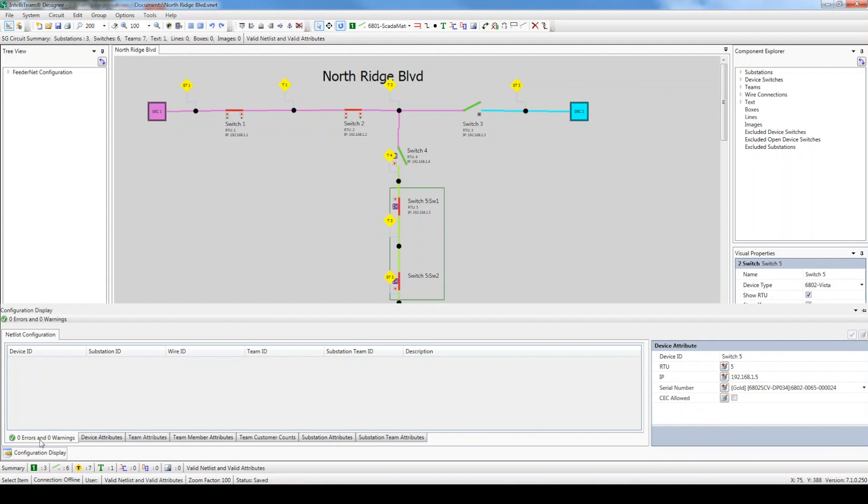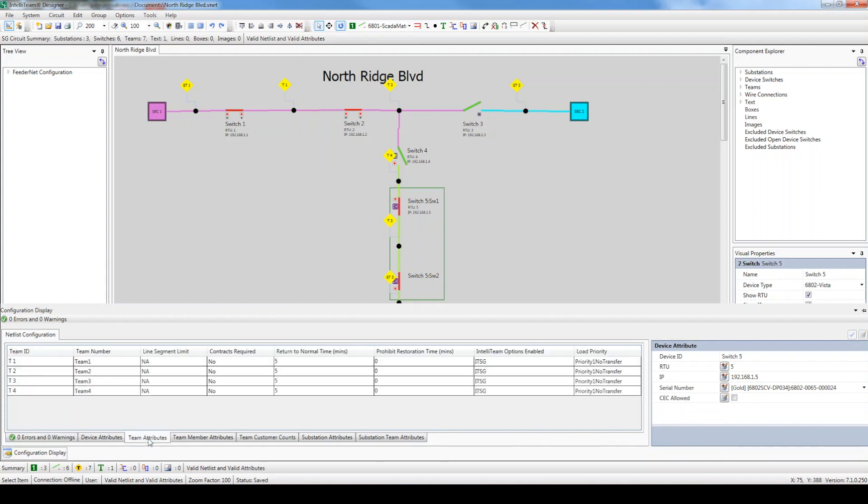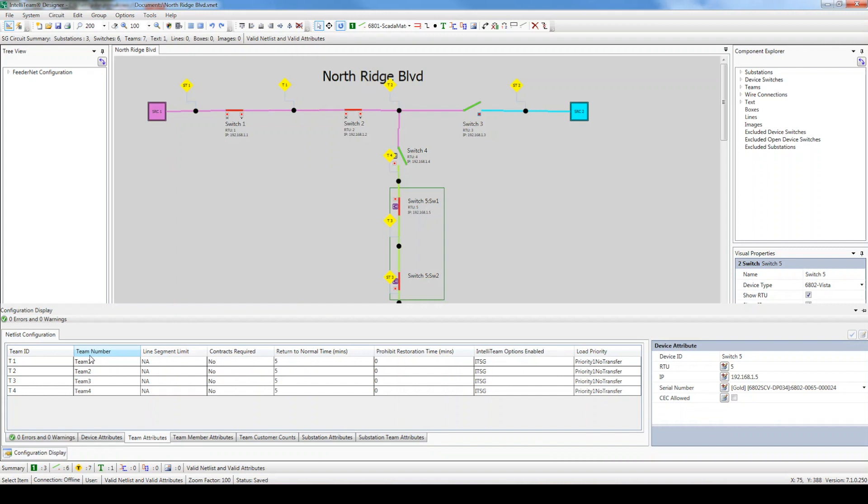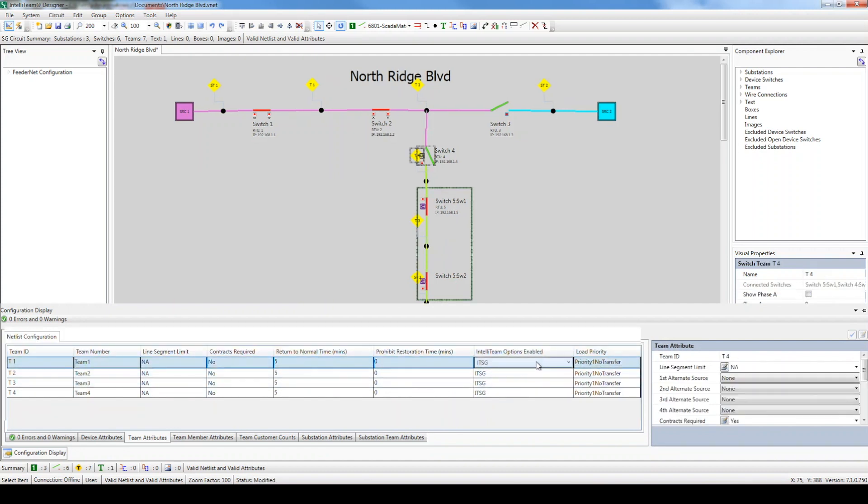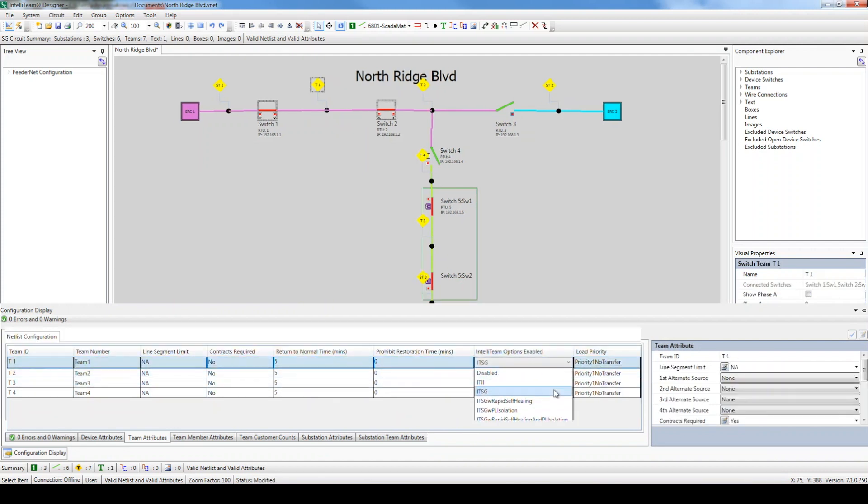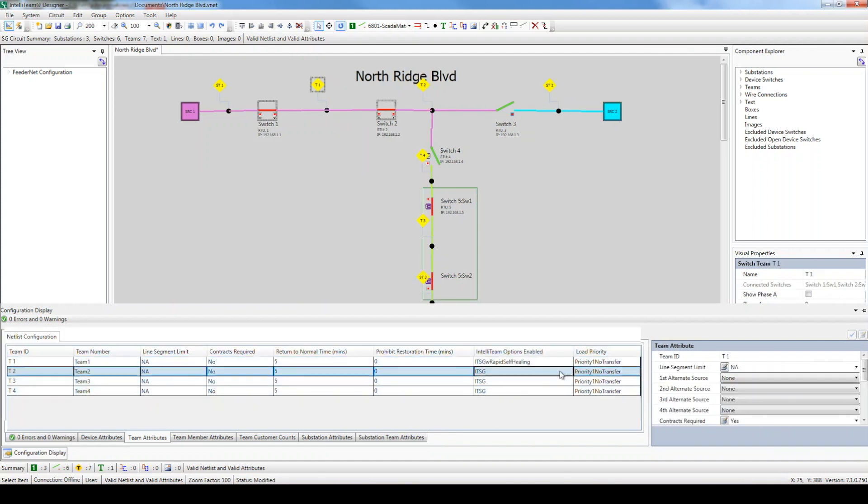Next, click the Team Attributes tab. This is where you configure the settings related to each team of devices. The first two columns display the team identifiers, which are generated during the validation process. The IntelliTeam Options Enabled setting is used to select which IntelliTeam features to enable. Since we plan on using Rapid Self-Healing but not Phase Loss Isolation, let's select ITSG with Rapid Self-Healing.